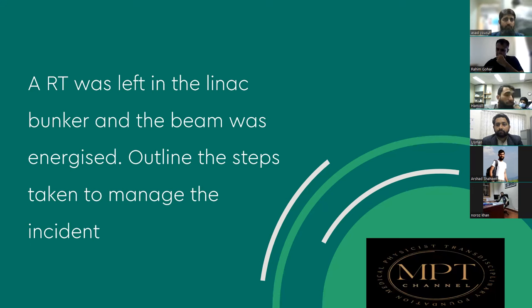And we can do the in vivo dosimetry for that as well. Not in vivo dosimetry, but dosimetry by simulating that incident, placing an OSL or a TLD at that position, or a chamber, to calculate how much dose that person could get, and also we should monitor how much time he spent in the bunker. You will check your backup counter. Backup counter, yes.